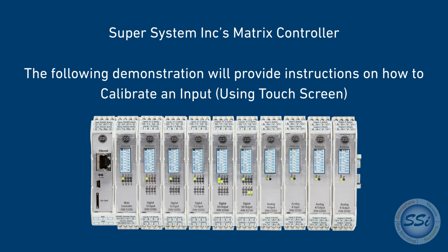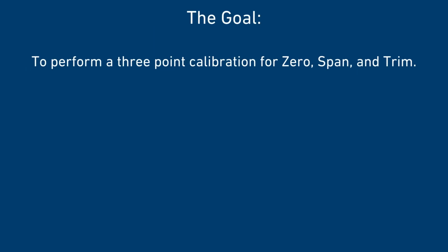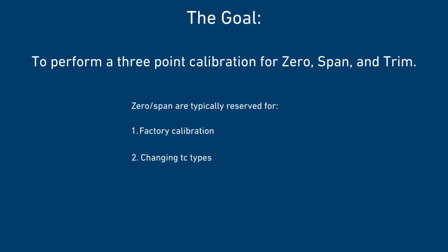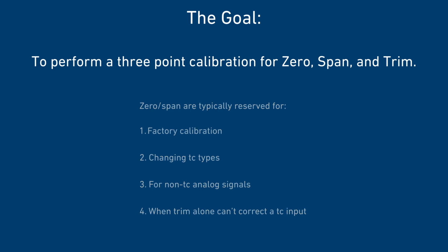Welcome. Today, we are going to calibrate a matrix input. Most field calibrations skip the zero and span and only perform the trim calibration. Zero span are typically reserved for 1. Factory calibration, 2. Changing TC types, 3. For non-TC analog signals, and lastly, 4. When trim alone can't correct a TC input.